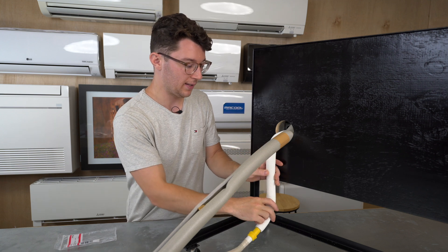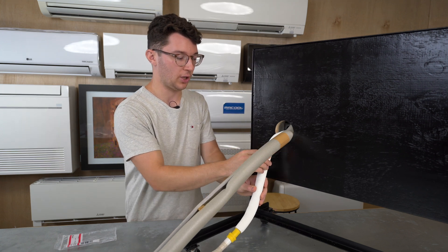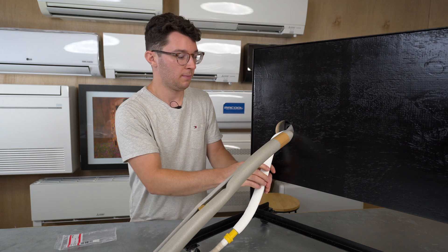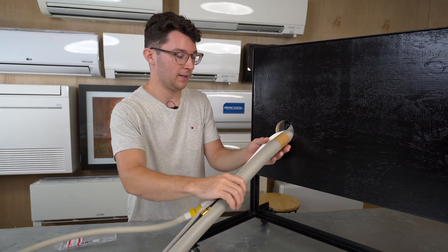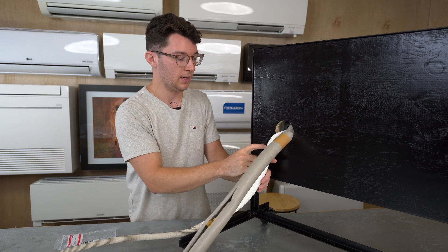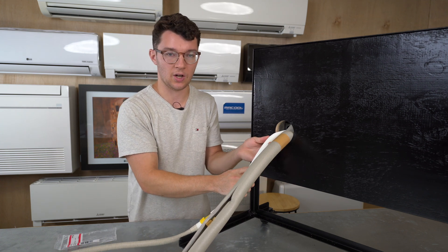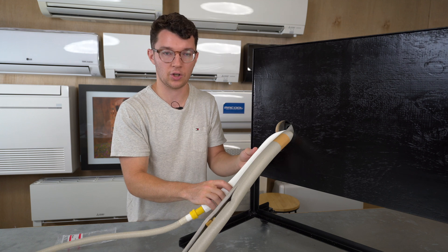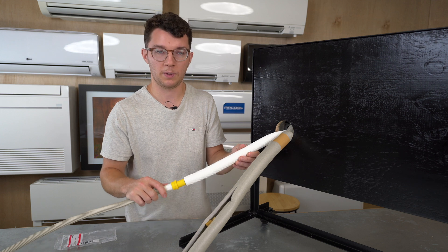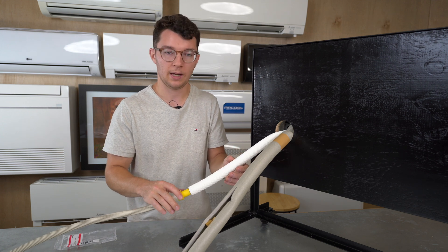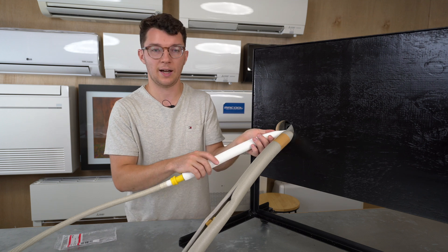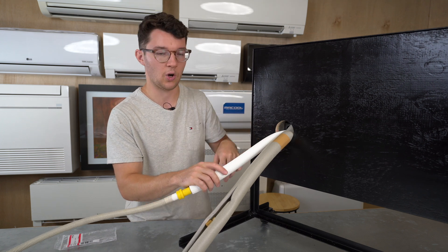You just run this downward making sure that your condensate hose isn't squeezed or pinched, making sure that the refrigerant line that is going alongside the condensate hose isn't squeezing that condensate hose in a way that would eventually clog it or pinch it where there would be restriction to your flow. Make sure you're running it alongside parallel and it's not squeezed up along this hole.